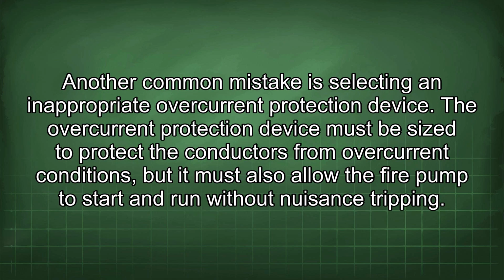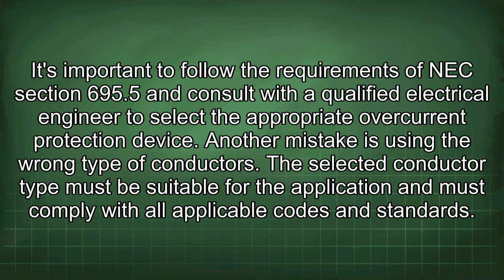Another common mistake is selecting an inappropriate overcurrent protection device. The overcurrent protection device must be sized to protect the conductors from overcurrent conditions, but it must also allow the fire pump to start and run without nuisance tripping. It's important to follow the requirements of NEC section 695.5 and consult with a qualified electrical engineer to select the appropriate overcurrent protection device.